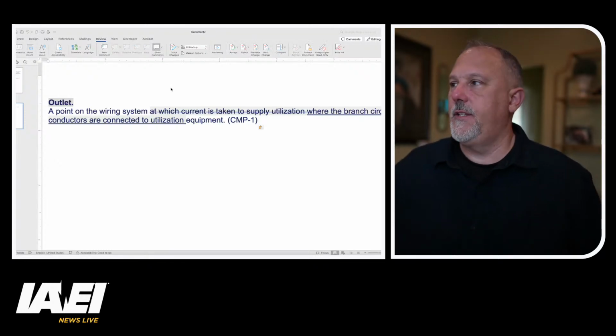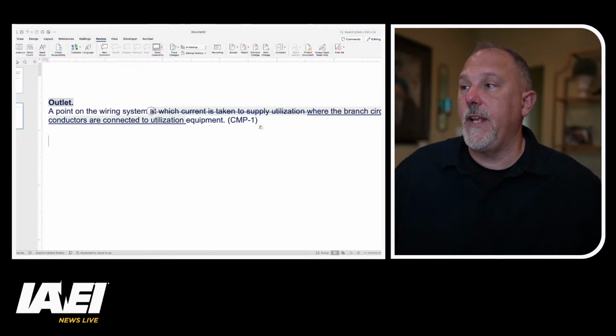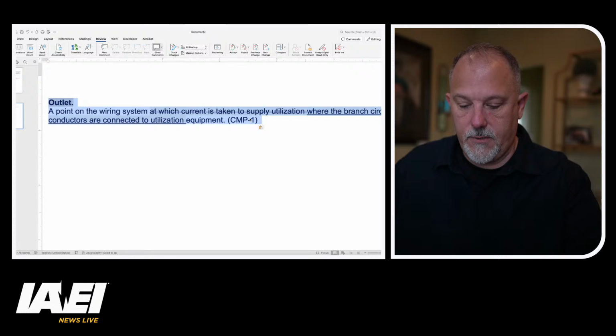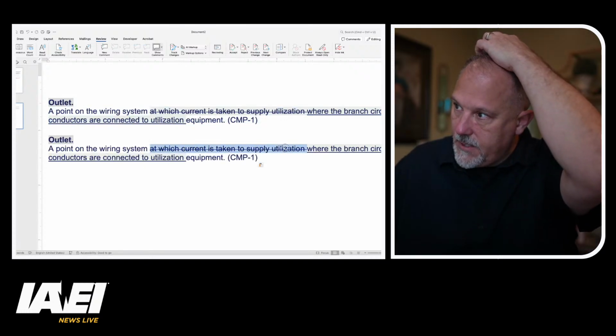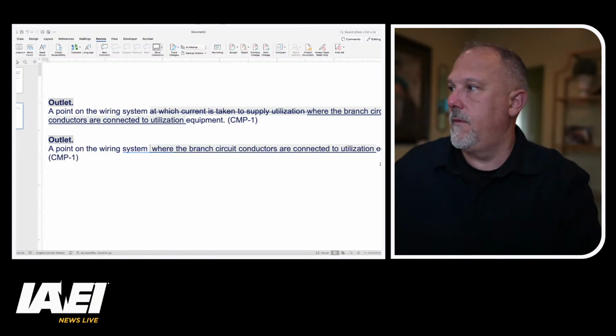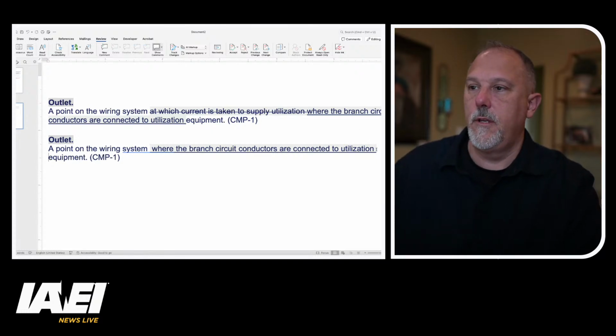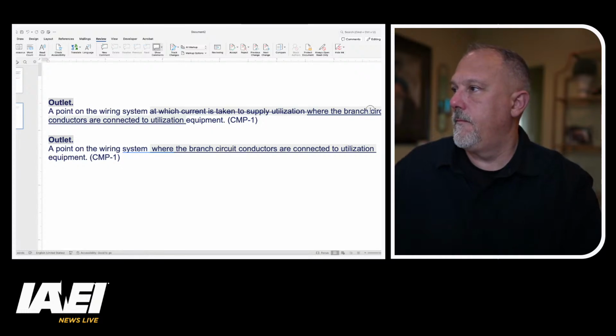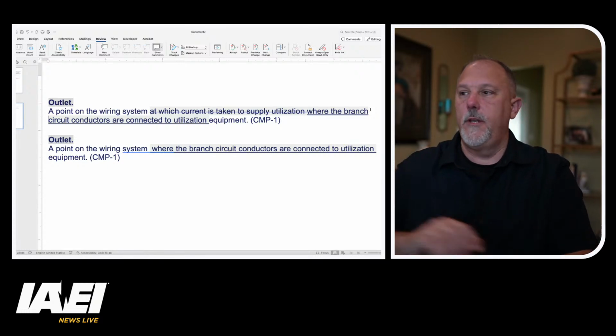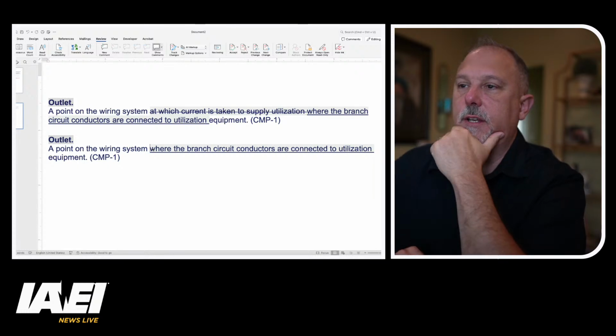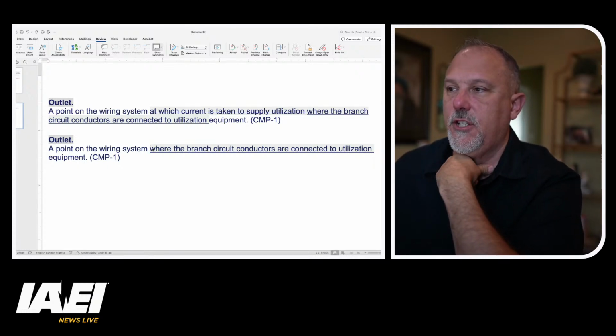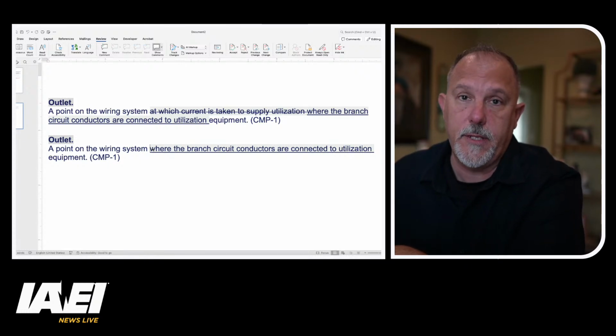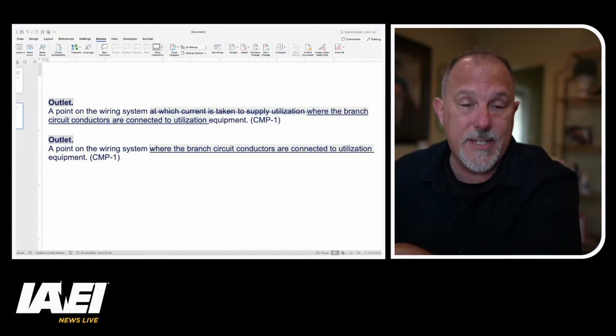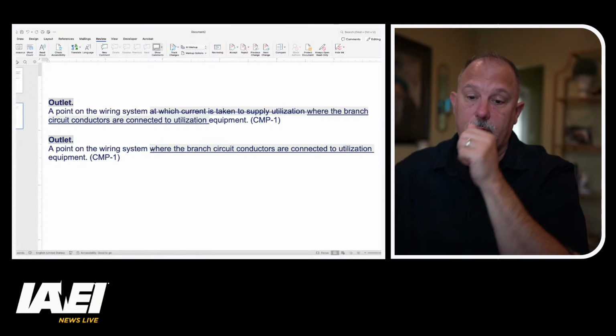So what the language says is a point on the wiring system, and they removed "at which current is taken to supply utilization equipment." They removed that. So let's just do what it says. What it will end up saying is this: a point on the wiring system where the branch circuit conductors are connected to utilization equipment. So it has to go straight to utilization equipment, and a receptacle is not utilization equipment. So an outlet for a receptacle is not an outlet. So then that puts in question, what is a receptacle outlet? Because they use the term outlet in the defined term for receptacle outlet.